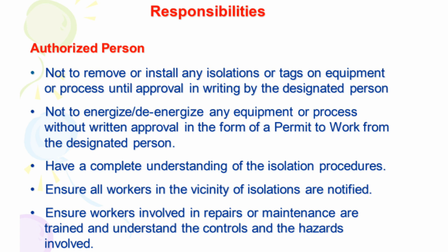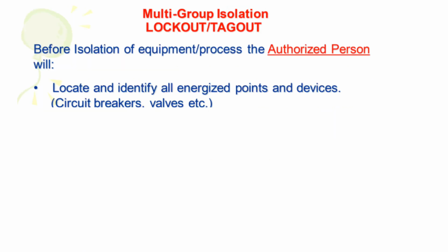Responsibilities of the authorized person: not to remove or install any isolations or tags on equipment or process until approval in writing by the designated person. Not to de-energize any equipment or process without written approval in the form of a permit to work from the designated person. Have a complete understanding of the isolation procedures. Ensure all workers in the vicinity of isolations are notified. Ensure workers involved in repairs or maintenance are trained and understand the controls and the hazards involved.